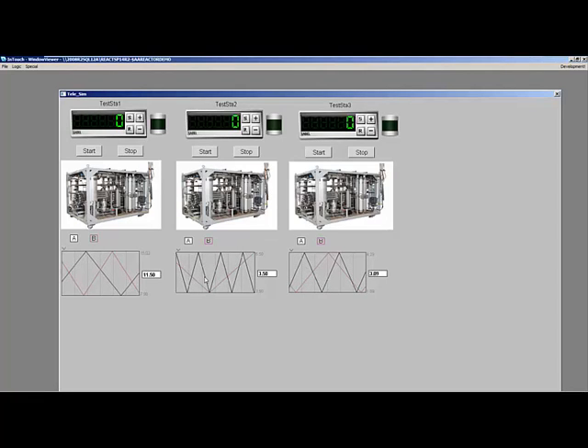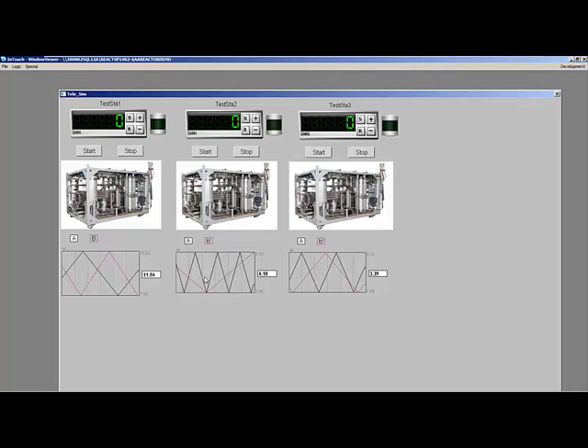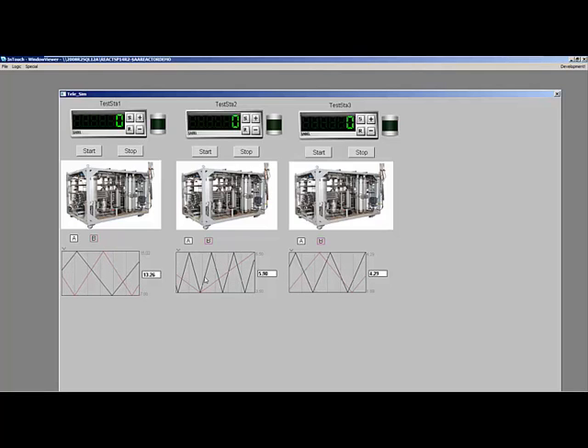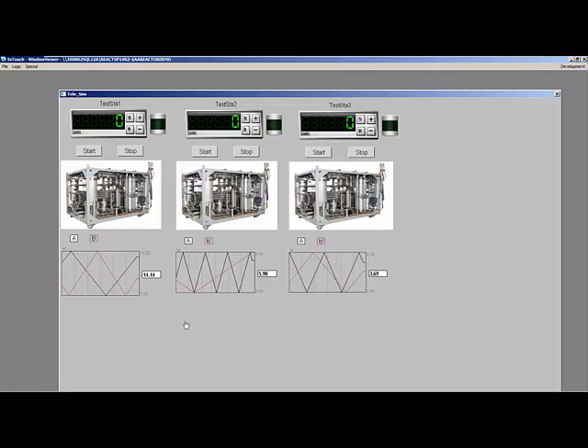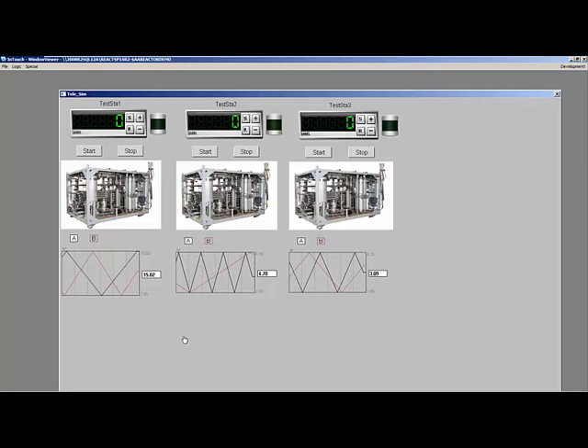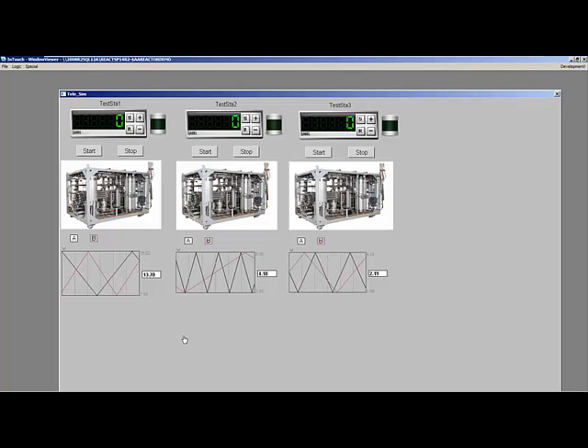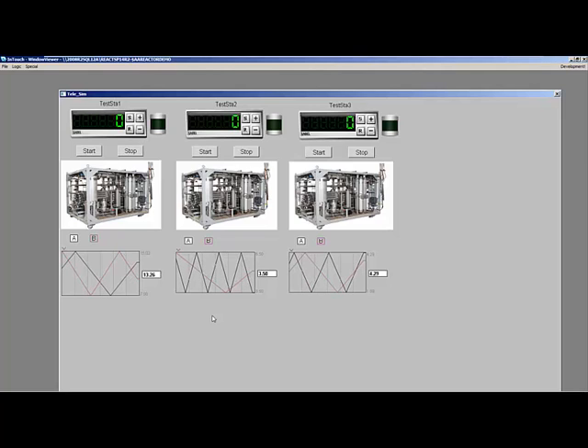In this example scenario we're going to capture some temperatures, pressures, and flows and log that to the Wonderware Historian against a specific test ID and a specific serial number for the piece of equipment being tested. The whole concept is to extract this information from the Wonderware Historian based on serial number and test ID. We're going to use the Wonderware Historian event system to detect the start of a test, log the start time, the ID, and the serial number to a separate table in the database.